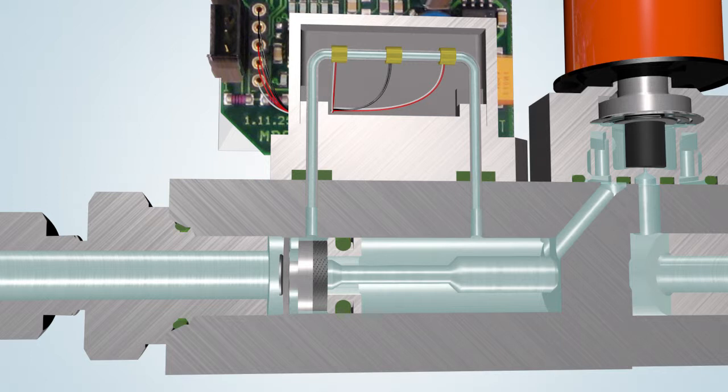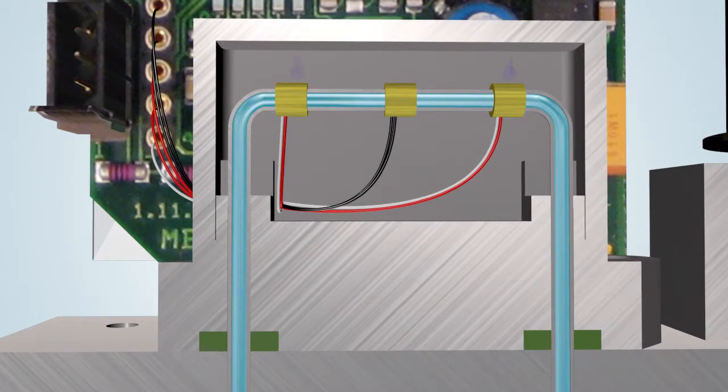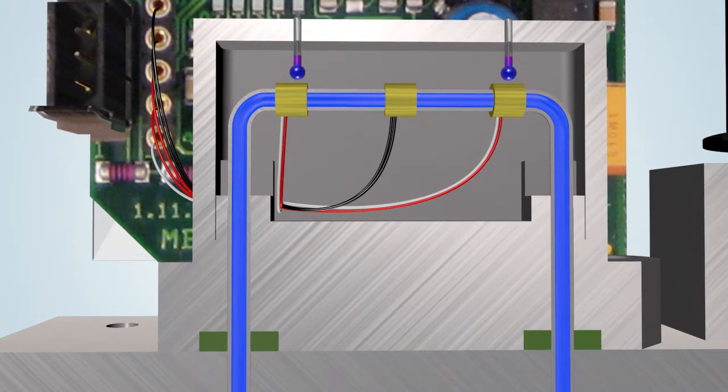Once the instrument has been connected to the process line, the pre-pressure can be set. The body and the sensor are now filled with gas. The sensor consists of a thin capillary tube fitted with a heater and two temperature recorders. The heater heats the tube.